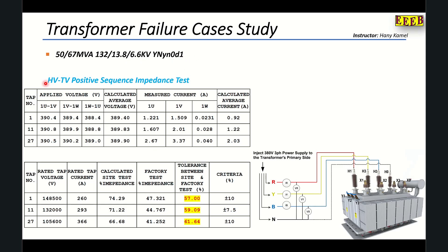When we perform the HV to tertiary positive sequence short circuit impedance test, we apply three-phase voltage with neutral to the HV side of the transformer — H1, H2, H3, and H0 — and we short the tertiary winding. In this case we measure the short circuit impedance positive sequence between the HV winding and the tertiary winding.